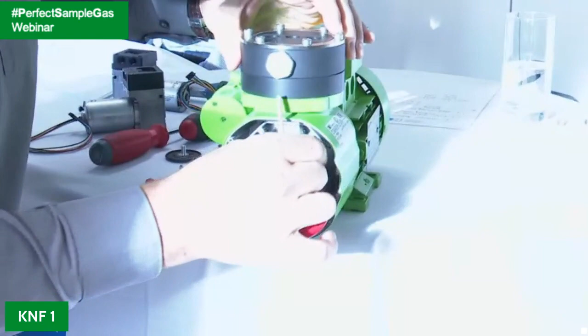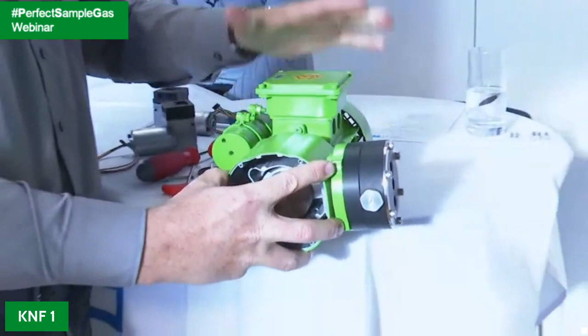It's a little tricky to get the screws out - that shouldn't happen, a screw falling down. Once you've removed all the screws, you're able to rotate the head of the pump in 90 degree increments. If you mount the pump this way, it's recommended to put the head parts facing down, so the condensate has a smooth path to drain out of the pump. I have to be careful the pump doesn't fall to the ground. Then it's the same procedure in reverse - just reinstall the 4 screws and reinstall the cabinet plate.